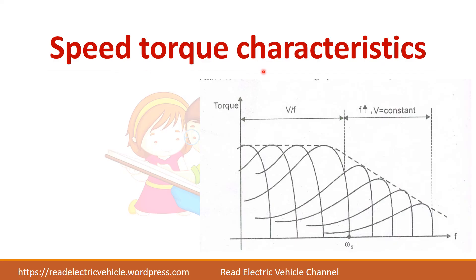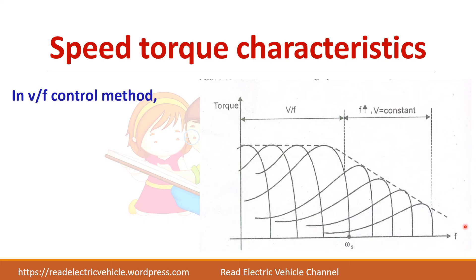Looking at the speed-torque characteristics: up to base frequency, the V by F ratio is maintained constant, so maximum torque also remains constant. After base frequency, frequency is increased with voltage held constant, causing torque to decrease. So torque will decrease after base frequency.